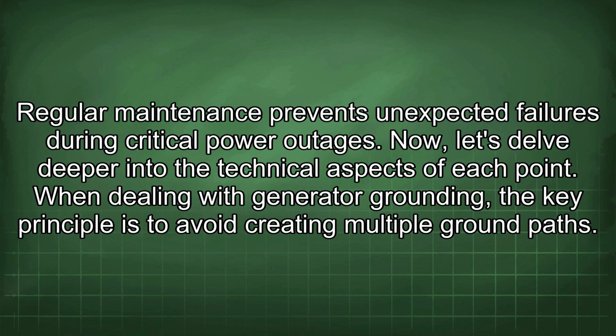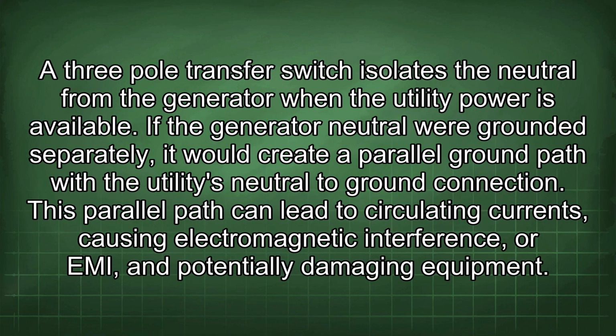Now let's delve deeper into the technical aspects of each point. When dealing with generator grounding, the key principle is to avoid creating multiple ground paths. A 3-pole transfer switch isolates the neutral from the generator when the utility power is available.